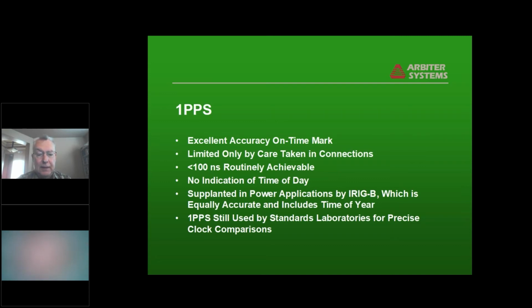Problem with 1 PPS is it's good for a frequency measurement, which is what the time labs are interested in, but it doesn't really give you any information above and beyond that. Time of day, for instance. So it's been supplanted by IRIG-B for quite some time now in power systems, because IRIG-B is also a digital system with the same kind of accuracy in the rising edge of the pulse, but it does include the time of year.